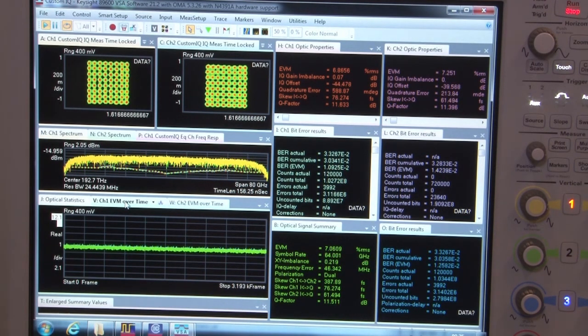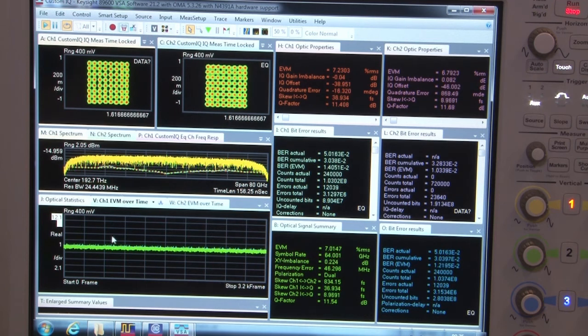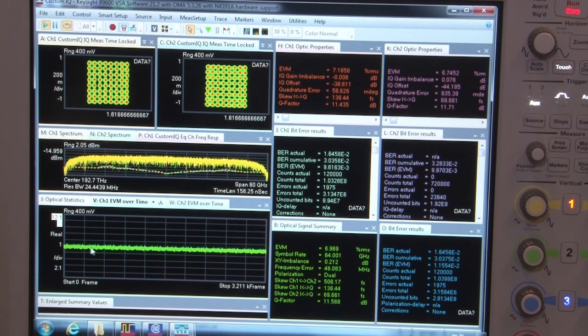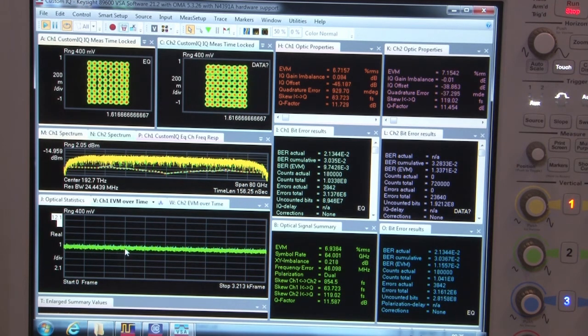The OMA software allows the analysis of signals in various modulation time domain or frequency domain. In this picture here I show the EVM value over time. So if you want to do a long-term experiment you can check or control the error vector magnitude over a longer time to identify errors in the transmitter.